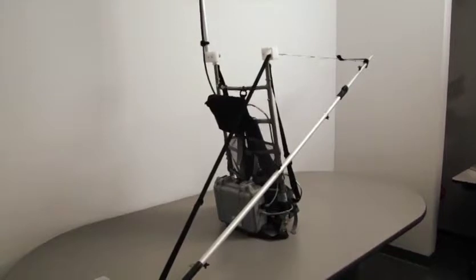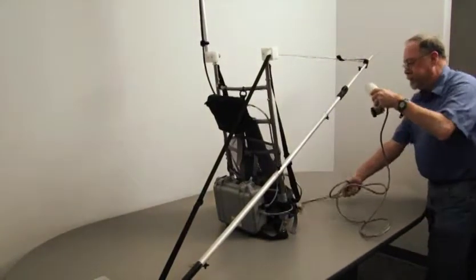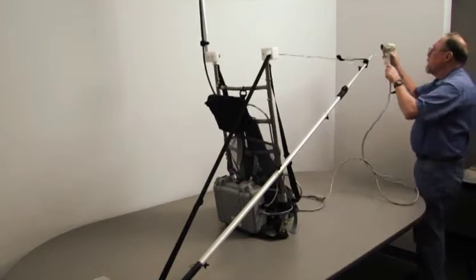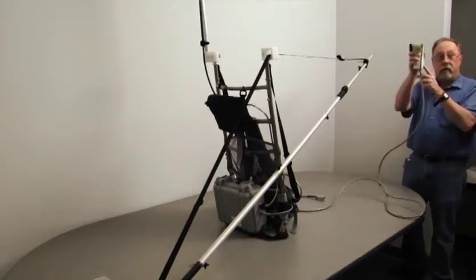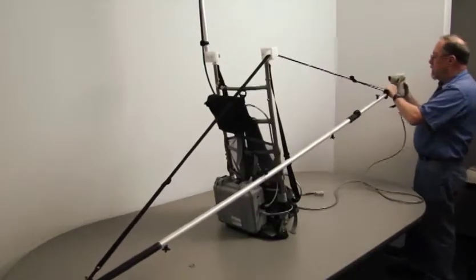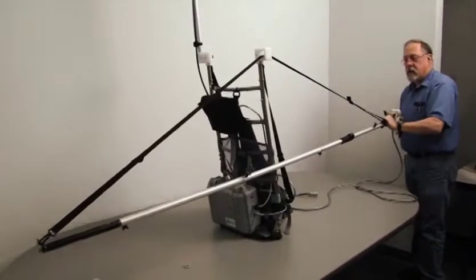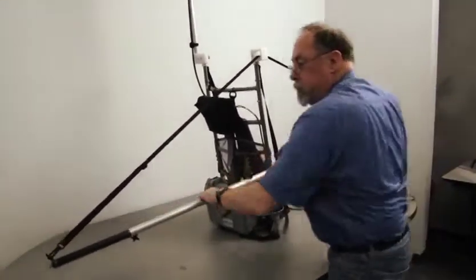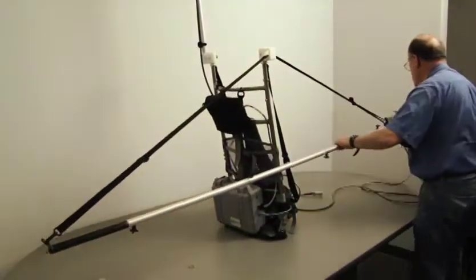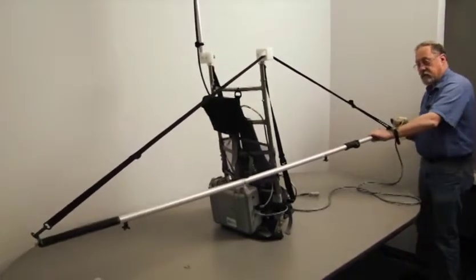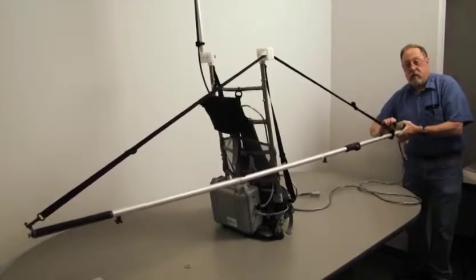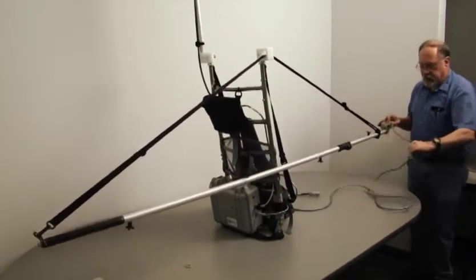Here's the sensor removed from the case. At this particular location, the correct orientation for the sensor is vertical, not tipped to one side or the other. So we're going to mount the sensor on the end of the staff. Line things such that the sensor is naturally in a vertical position, and then we tighten the sensor clamp to keep the sensor in place.